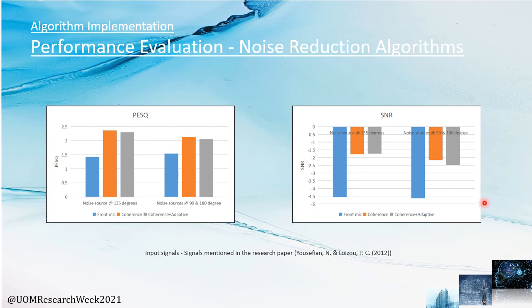We combined the two noise reduction approaches and here are the results: after only stage 1, and after the combination of stage 1 and 2. As input signals, we used 0 dB SNR signals with multi-talker babble and speech-shaped noise types. The graph shows an average of SNR and PESQ values for those signals, with noise sources at 135 degrees and two noise sources at 90 and 180 degrees. We could not see a clear increase in SNR and PESQ values from the algorithm combination, but we could hear an improvement in the output. We therefore decided to test the performance further using subjective metrics.